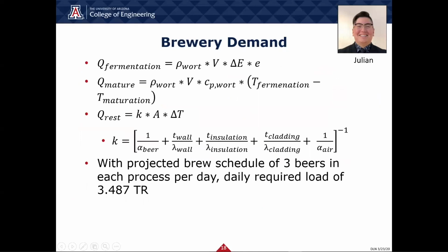The analysis for brewery demand took into account the 3 processes in beer production that require cooling: fermentation, crashing, and holding the finished beer at a constant temperature. We then used principles from thermodynamics and heat transfer to calculate the chilling demand of the brewery for a particular load case. We found that the daily required cooling load was 3.487 tons of refrigeration.